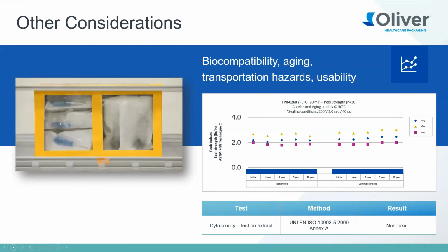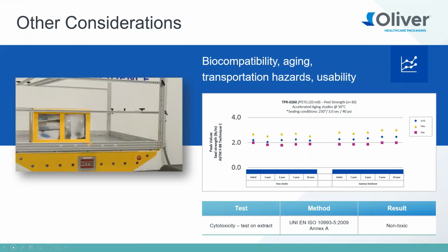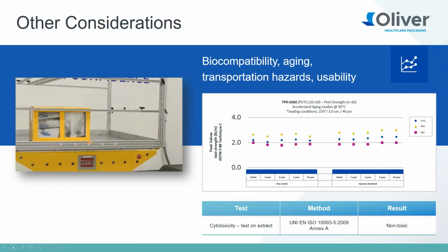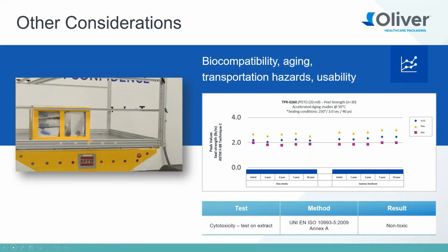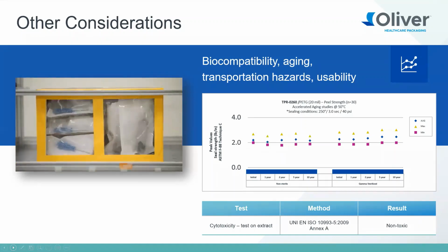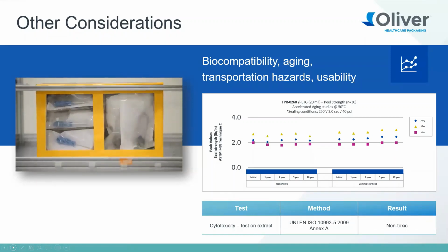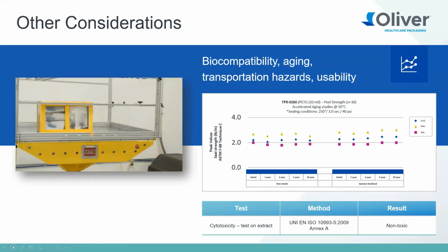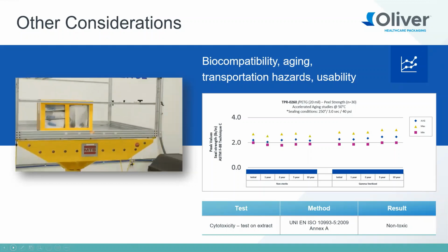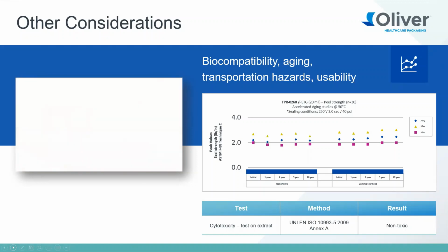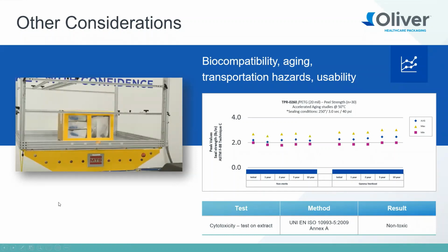It's good to get an understanding of aging and compatibility with the sterilization modes that you're using. So the graph in the middle on the right there is basically just showing, work with your suppliers to get a basic understanding of sterilization compatibility, and that over time, they're not going to degrade. So this is just a simple seal curve, or not a seal curve, but kind of the output of seal strength out to 10 years post sterilization. So that's always good to have.